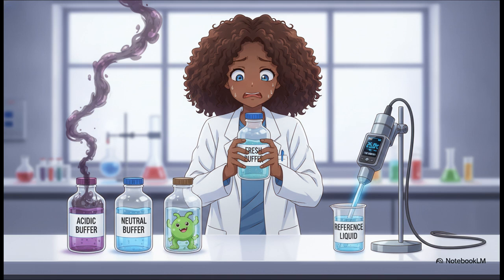To combat these physical realities, we've got some rapid-fire essential rules for handling your buffers. First, discard your used buffer immediately. Don't pour it back into the bottle. Second, keep your bottles tightly capped. Remember how we exhale CO2? Well, atmospheric carbon dioxide will literally dissolve straight into an alkaline buffer, turning it acidic and ruining it completely. Third, watch out for airborne mold spores. They absolutely love growing in neutral buffers. And finally, always use automatic temperature compensation, or ATC, because temperature fundamentally changes that Nernstian slope we talked about.